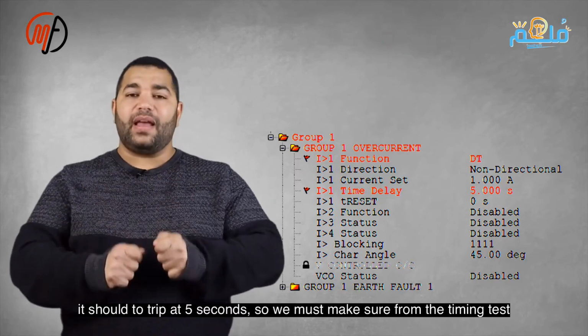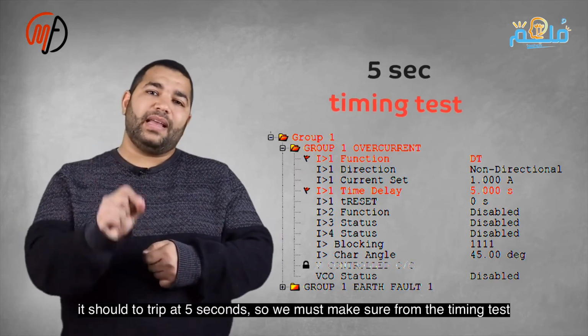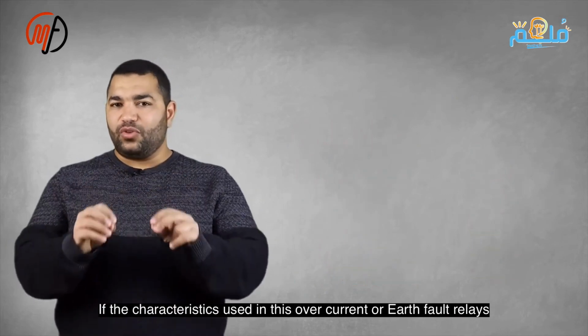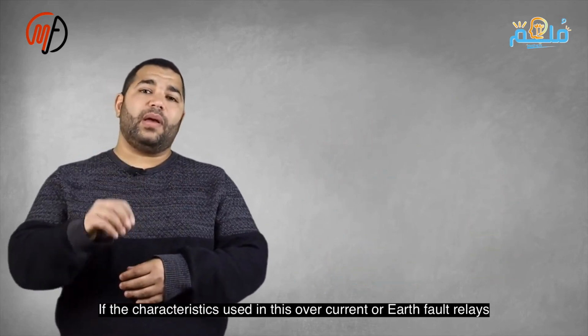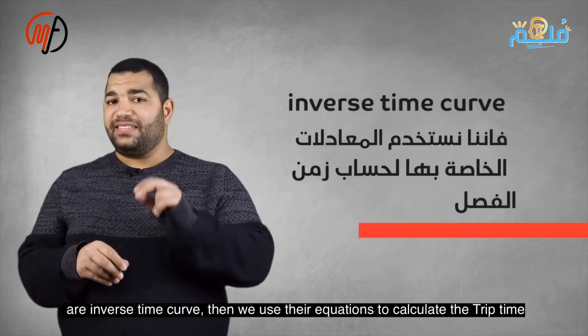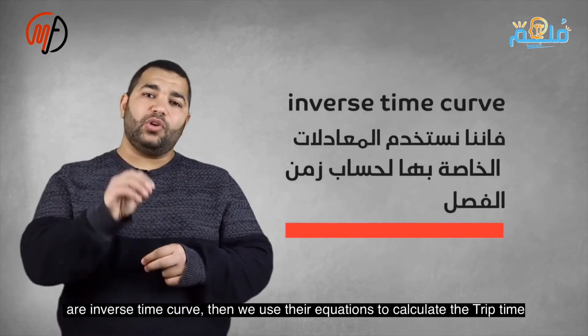We calculate trip times at 2, 3, and 5 times the setting current, using either the normal inverse equation or curve. Using inverse time curve equations, we calculate the trip time. TMS is needed for the trip time. Higher fault current means shorter trip time.